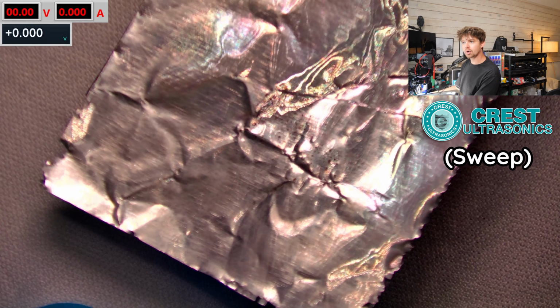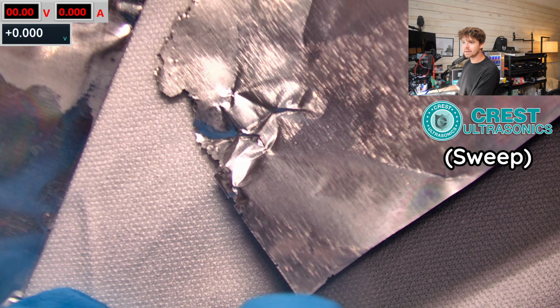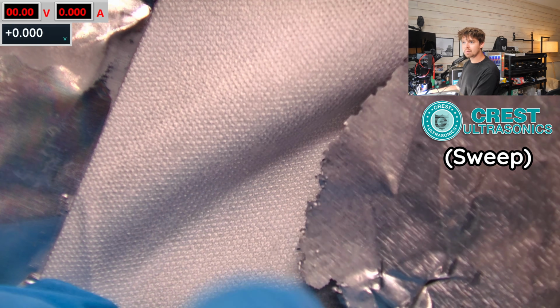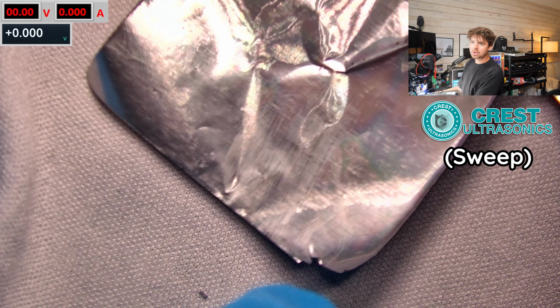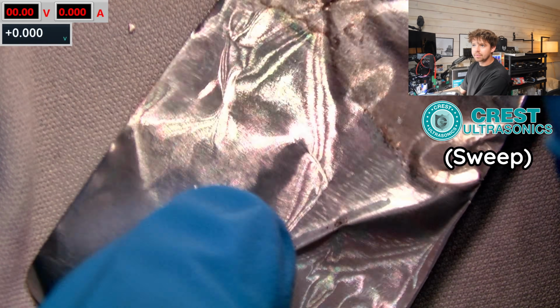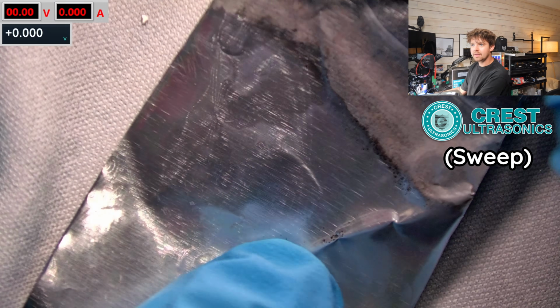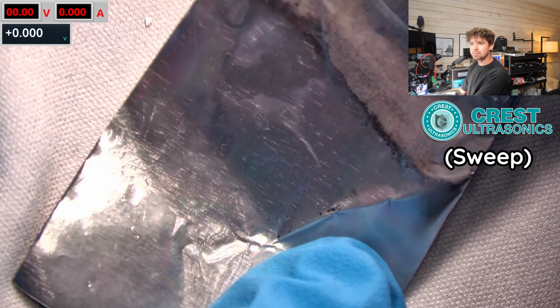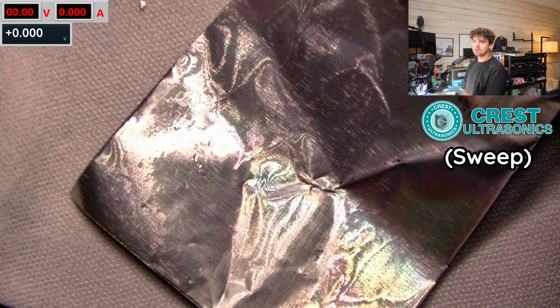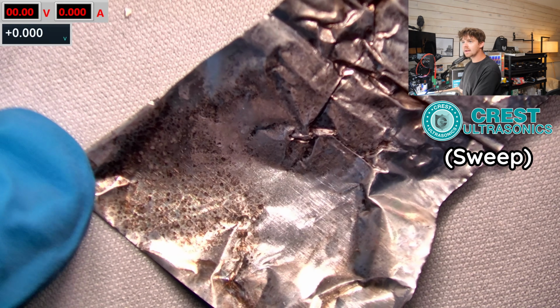This was on the corner. Here's another one that was on the edge. You can see that is clearly a little bit of a dead zone there, but you can see it ate through the bottom of this foil. We don't have as much eating away of the foil. On this one, you can see it's still made this whole entire part thin. So just because we don't have holes doesn't mean cavitation isn't occurring. It's just how aggressive the cavitation is.